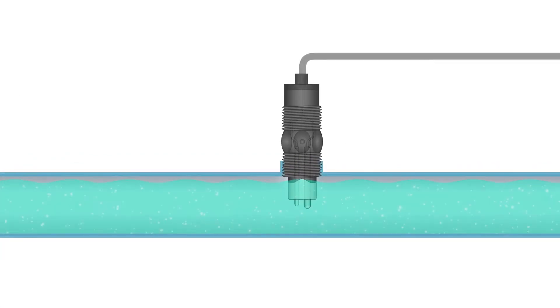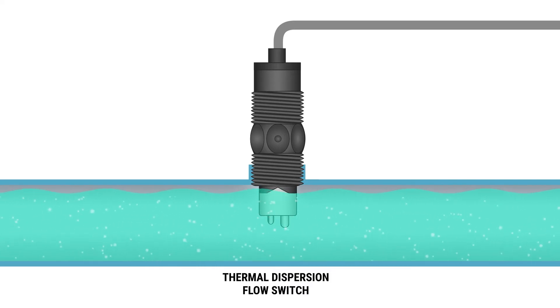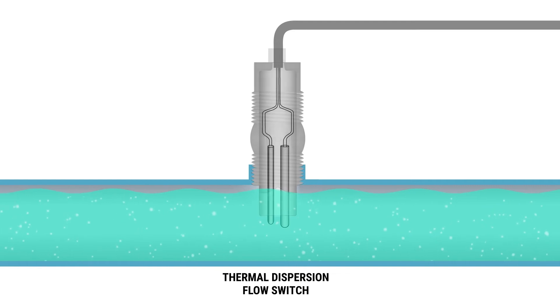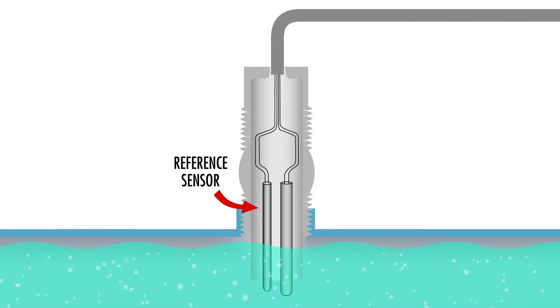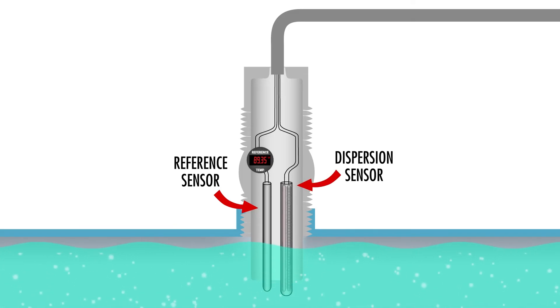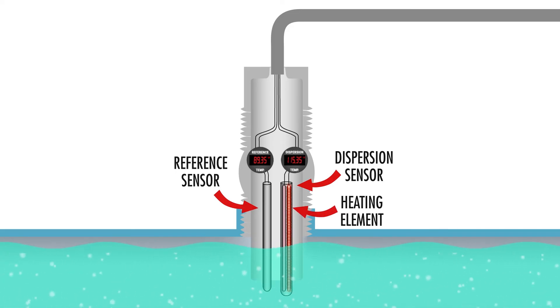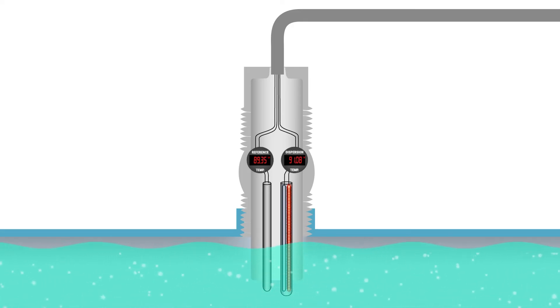Now let's look at a thermal dispersion flow switch. This solid state flow switch operates on the principle of heat transfer. A thermal dispersion flow switch consists of two temperature sensors. One sensor is the reference and measures the temperature of the media where the flow switch is immersed. The second temperature sensor is placed near a built-in heating element. As the flow rate of the media increases, it has a cooling effect on the heated sensor — the more the flow, the more the sensor is cooled.